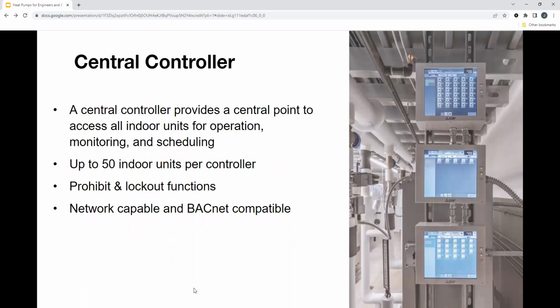And then you get into a central controller, right? So, hey, I have 56, 70 fan coils on this job. I want to communicate with it. I want everything in one central controller or one central location. This is what you would be selecting, right? So it can access all indoor units for operation, monitoring, and scheduling purposes. Each one of these controllers can hold up to about 50 indoor units, right? And then you can add expansion controllers on to get a total of 200 indoor units under one controller. It's touchscreen. You can play around with it and see exactly what the temperature is in each room and how they're operating. You can also go through the central controller and do prohibit and lockout functions.